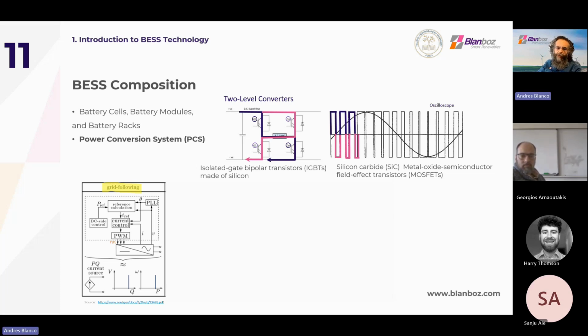In terms of the type of PCS, we have grid following. As the name says, the PCS follows the voltage of the source - it needs a voltage source to operate. So based on the voltage and current, it will follow the angle to adapt to whatever it needs to synchronize. Then you have grid forming, which can create its own voltage source.